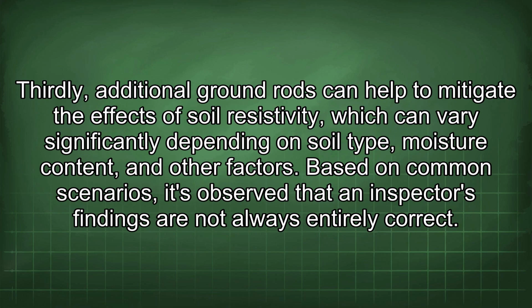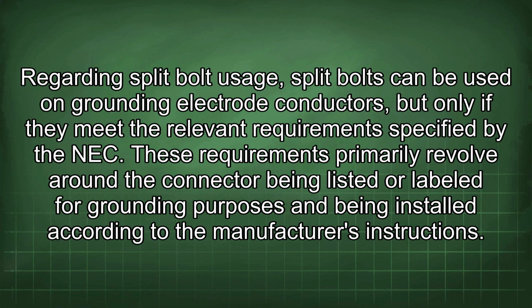Thirdly, additional ground rods can help to mitigate the effects of soil resistivity, which can vary significantly depending on soil type, moisture content, and other factors. Based on common scenarios, it's observed that an inspector's findings are not always entirely correct. Regarding split bolt usage, split bolts can be used on grounding electrode conductors, but only if they meet the relevant requirements specified by the NEC.